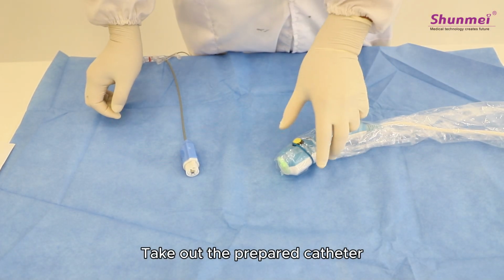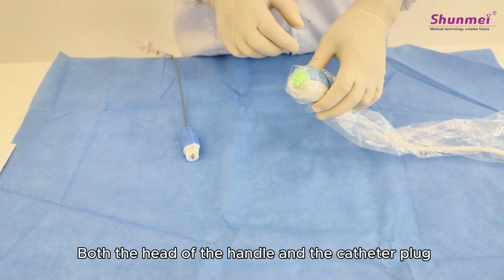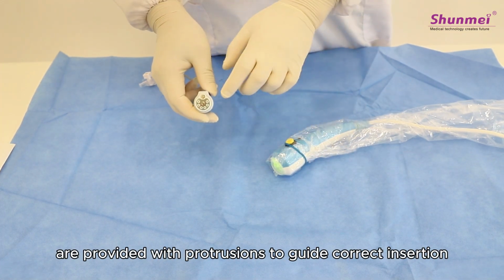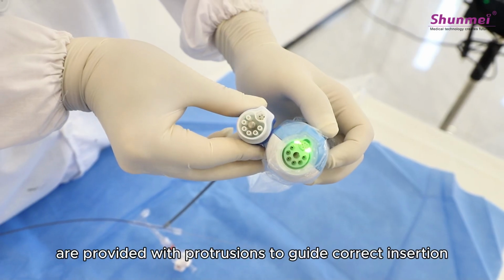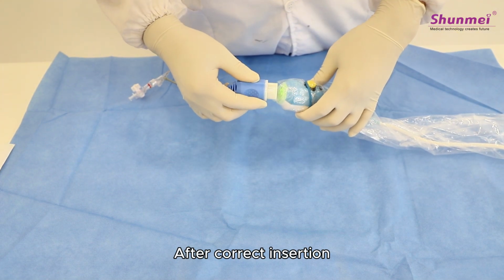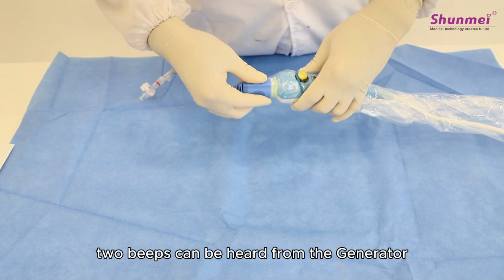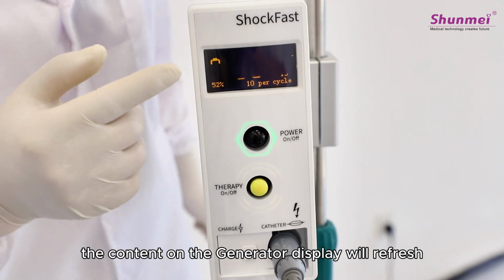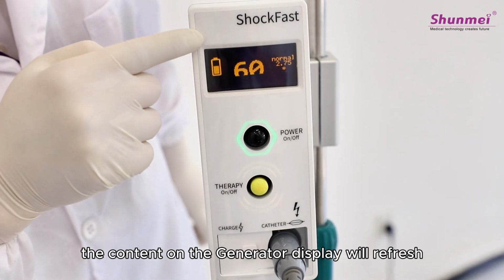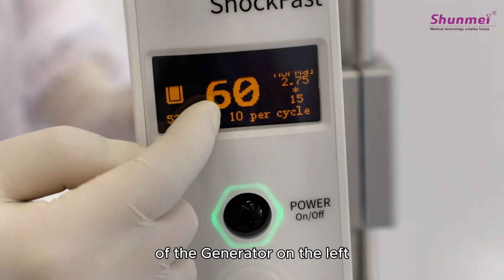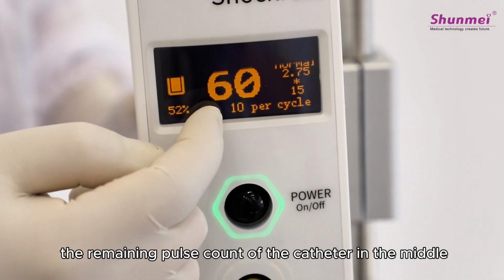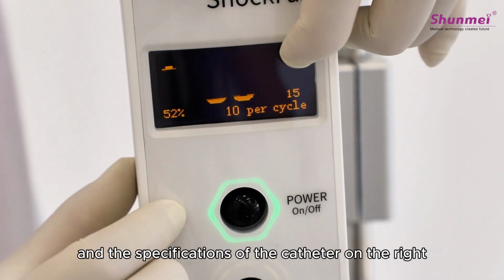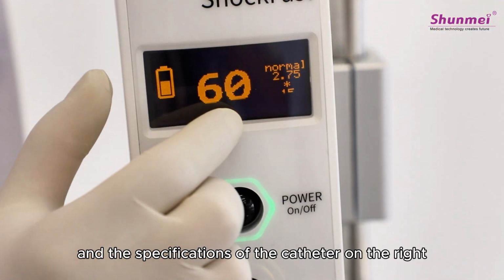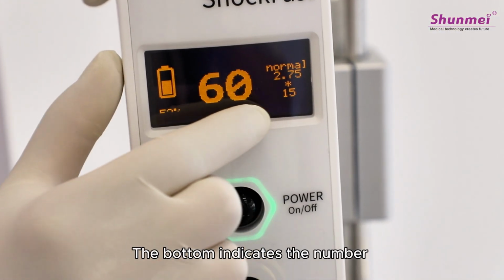Take out the prepared catheter. Both the head of the handle and the catheter plug are provided with protrusions to guide correct insertion. After correct insertion, 2 beeps can be heard from the generator. At this point, the content on the generator display will refresh, showing the remaining battery percentage of the generator on the left, the remaining pulse count of the catheter in the middle, and the specifications of the catheter on the right. The bottom indicates the number of pulses per complete cycle.